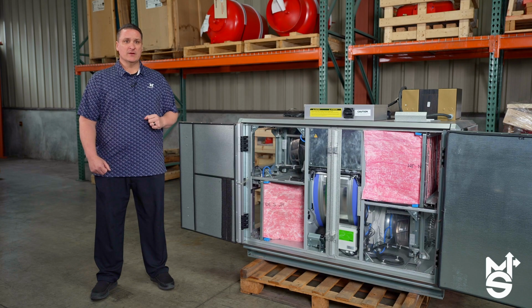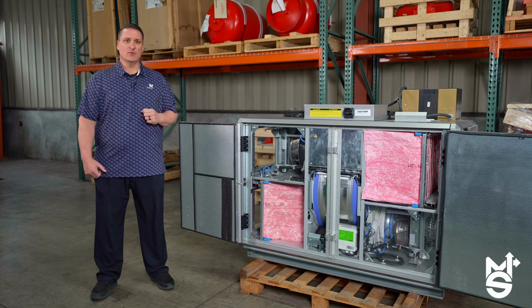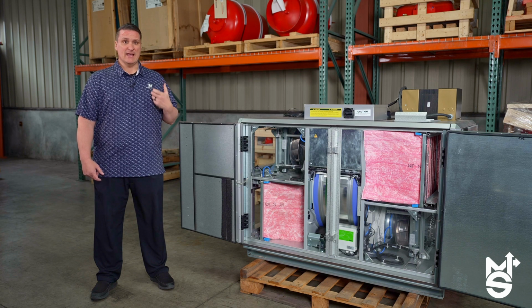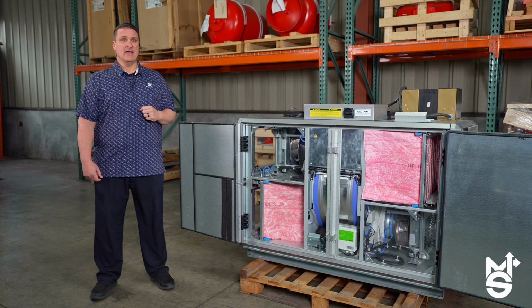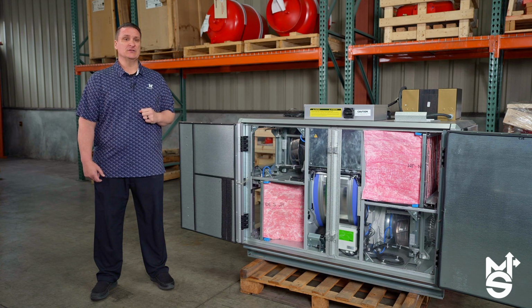So for humidity recovery and hygroscopic rotor control, Swegon offers some very precise control algorithms. Dehumidification reduces cooling loads in high humidity climates. In cold climates, humidity levels are critical to building health, and Swegon can help maintain that humidity by capturing it in the exhaust air and introducing it to the supply air.